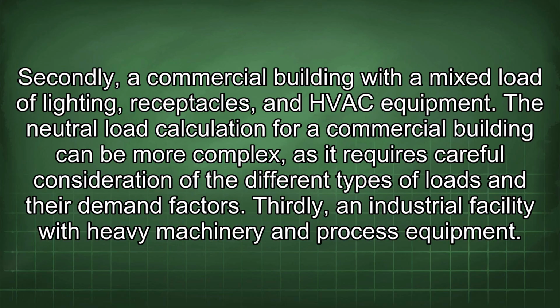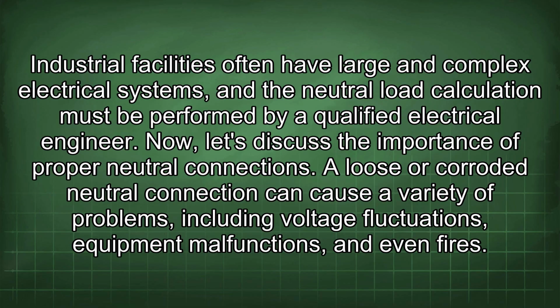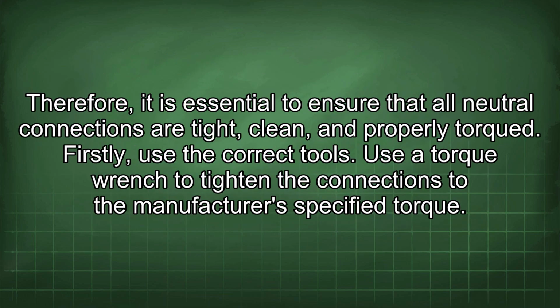Thirdly, an industrial facility with heavy machinery and process equipment. Industrial facilities often have large and complex electrical systems, and the neutral load calculation must be performed by a qualified electrical engineer. Now, let's discuss the importance of proper neutral connections. A loose or corroded neutral connection can cause a variety of problems, including voltage fluctuations, equipment malfunctions, and even fires. Therefore, it is essential to ensure that all neutral connections are tight, clean, and properly torqued.